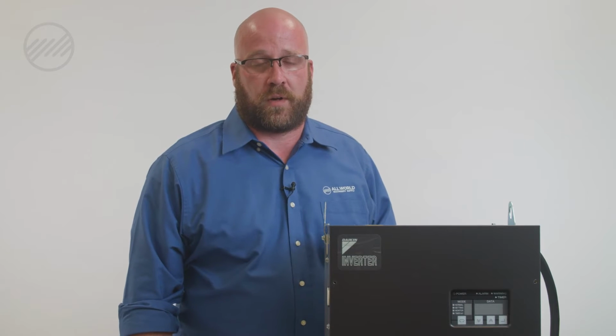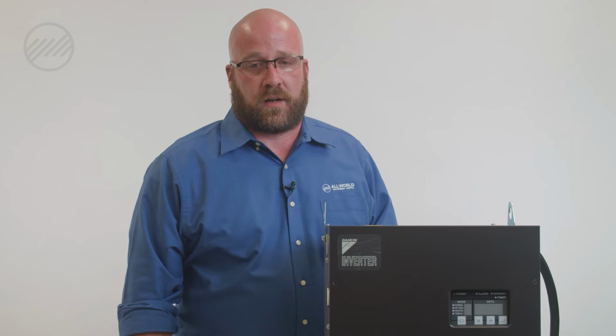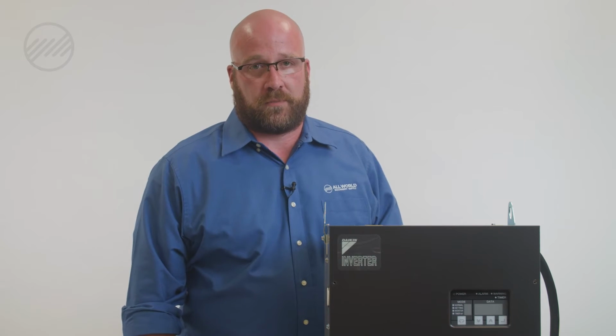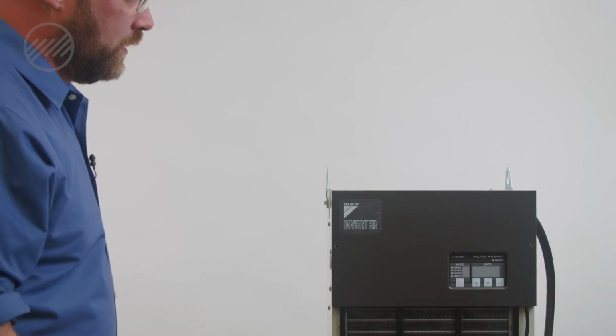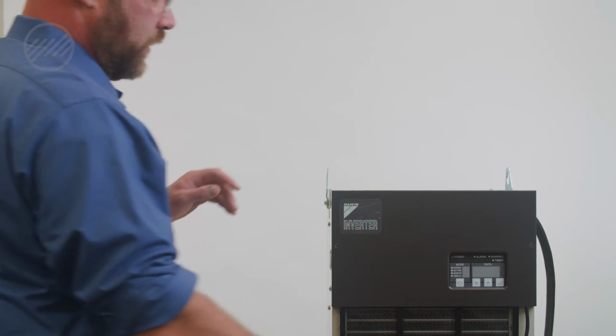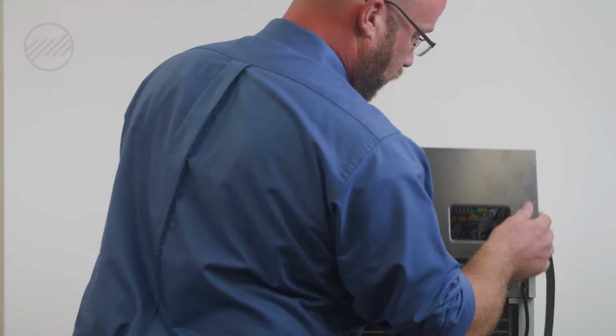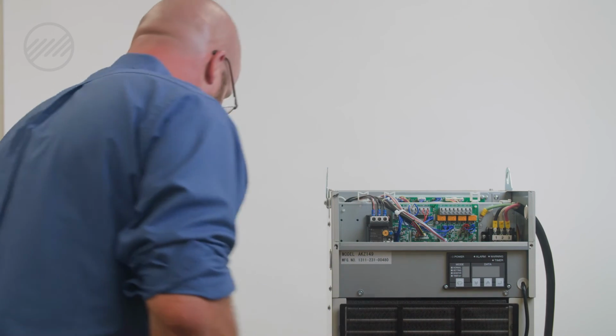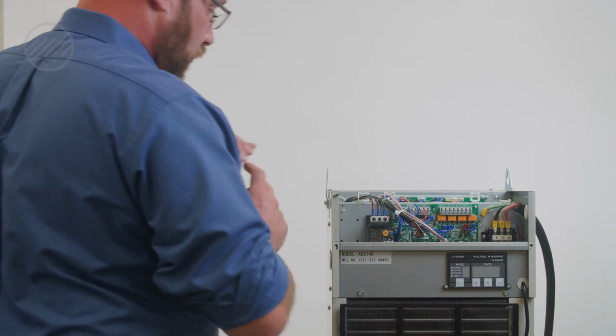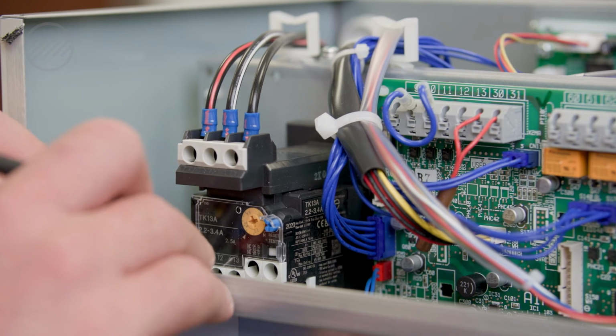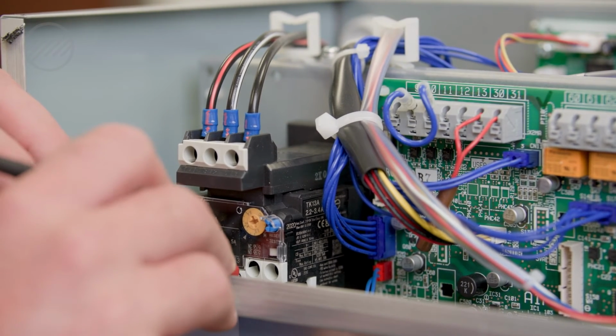When an EH alarm occurs, that is an issue with the pump or agitator, depending on the series of unit you have. The main causes are generally incorrect plumbing, a kinked line, a dirty filter, and/or a bad pump and motor. When an EH alarm occurs, first step, you need to remove the top cover, locate your pump wiring, check the wiring to ensure that you're getting proper voltage to the pump.